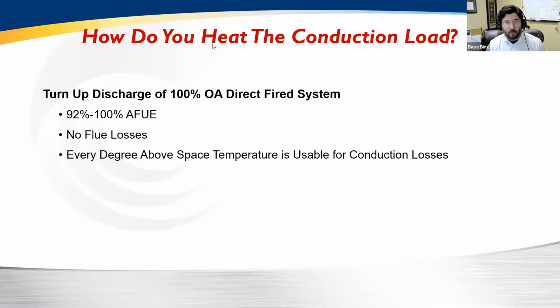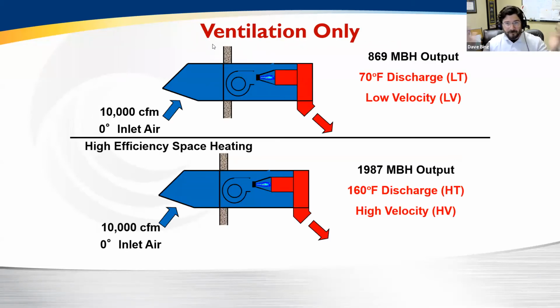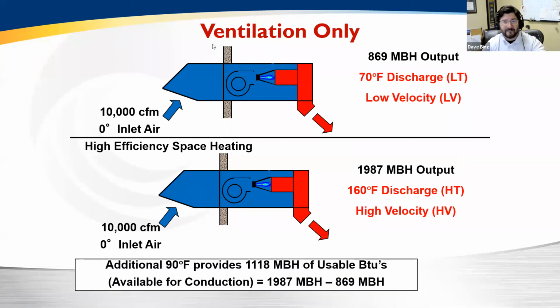Well, what HTHV does, and why it's energy efficient to utilize outside air, is that if I can turn my discharge temperature up to a high enough temperature where I have this extra heat available to counteract my skin losses, then I can not only cover my air load but also my conductive loads with the same device and the same burner technology, which is 100% combustion efficient. This is really the magic sauce to HTHV: I take a ventilation only device, but if I can dial the discharge temperature up as high as I can and get enough extra heat to counteract all my skin losses, with one device I can meet my ventilation requirements and my conductive loads, and do it with the most energy efficient way to combust gas and to heat. So what we do is we take a 10,000 CFM normal ventilation makeup air unit. By dialing up to 160, I now have an additional 1.1 million BTUs of heat available to heat skin losses.